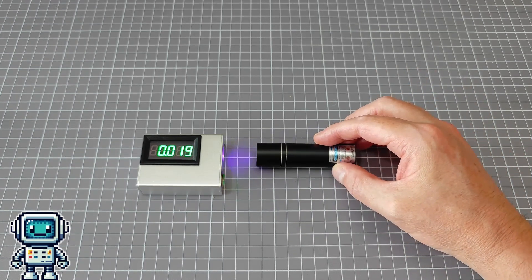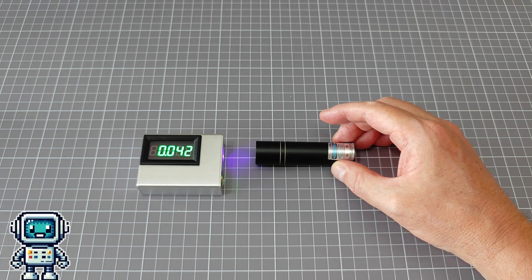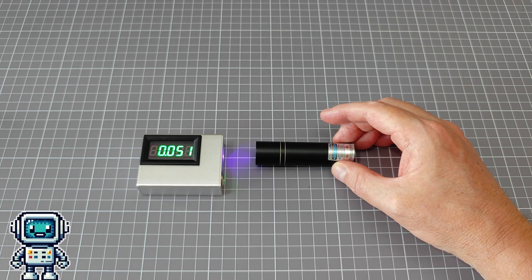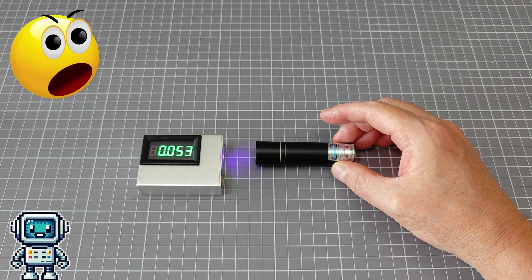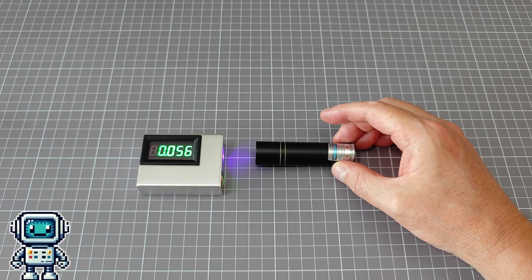This violet laser is a good example. The device label states it has a power output of less than 1 milliwatt, which means a user should not really need to wear eye protection. We would never have guessed that in reality the optical power output is close to 60 times higher than the specification, and for sure is a serious danger to unprotected eyes.